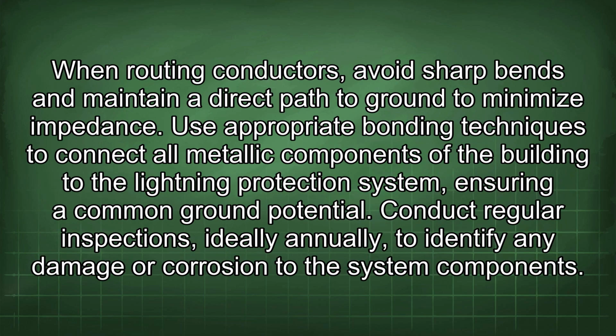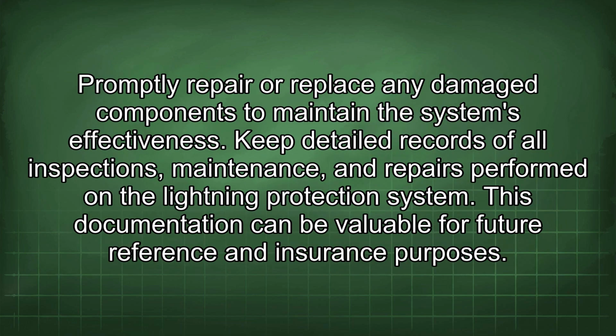When routing conductors, avoid sharp bends and maintain a direct path to ground to minimize impedance. Use appropriate bonding techniques to connect all metallic components of the building to the lightning protection system, ensuring a common ground potential. Conduct regular inspections, ideally annually, to identify any damage or corrosion to the system components. Promptly repair or replace any damaged components to maintain the system's effectiveness. Keep detailed records of all inspections, maintenance, and repairs performed on the lightning protection system. This documentation can be valuable for future reference and insurance purposes.